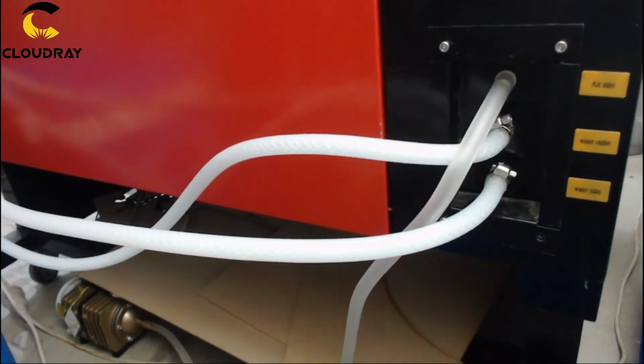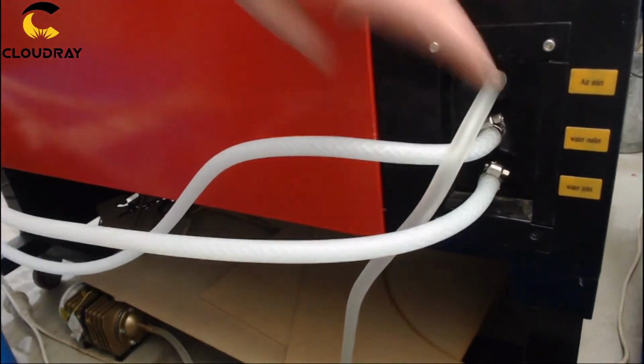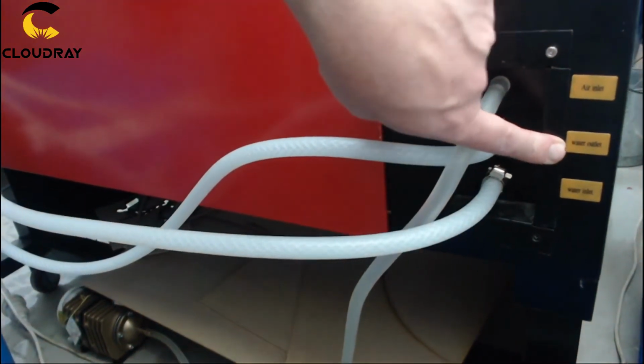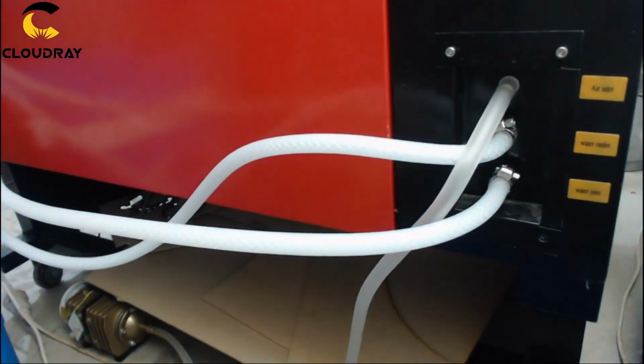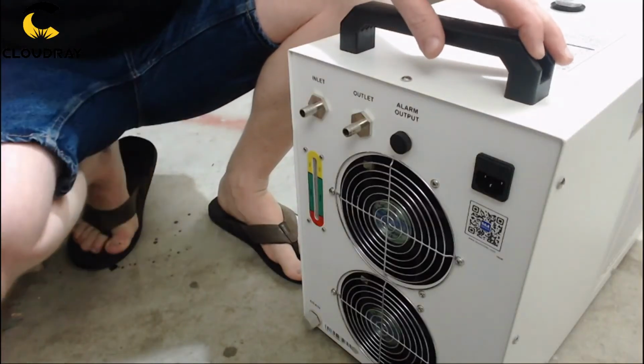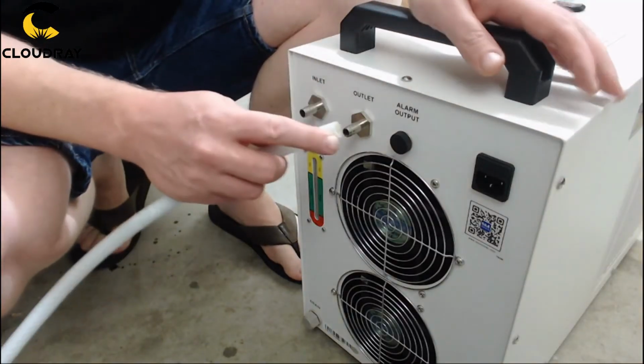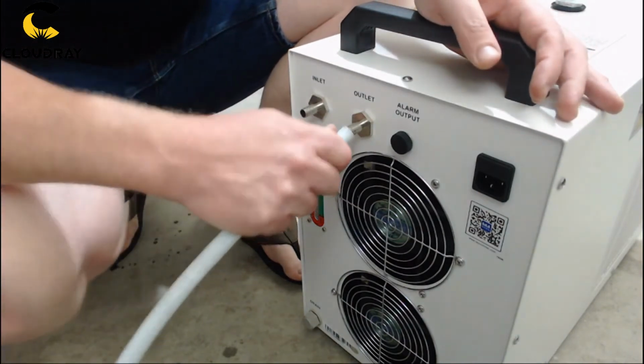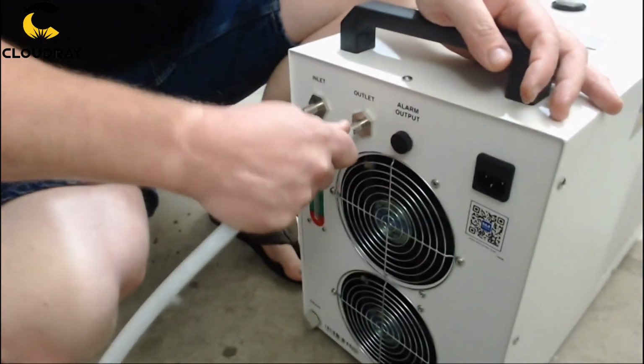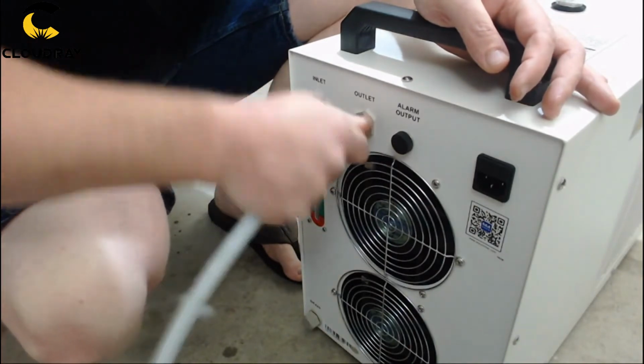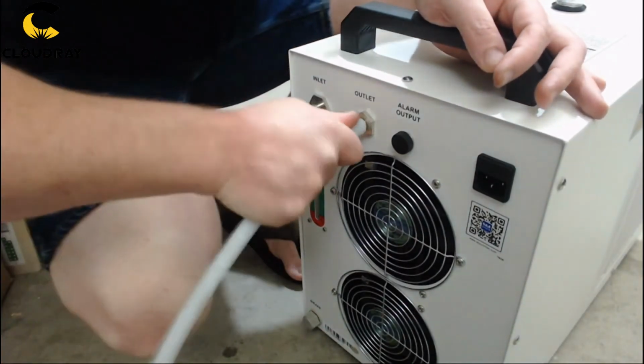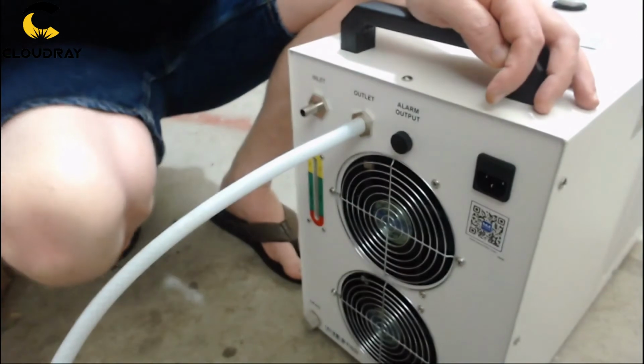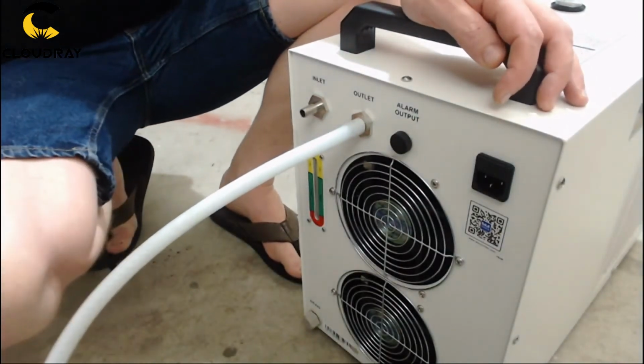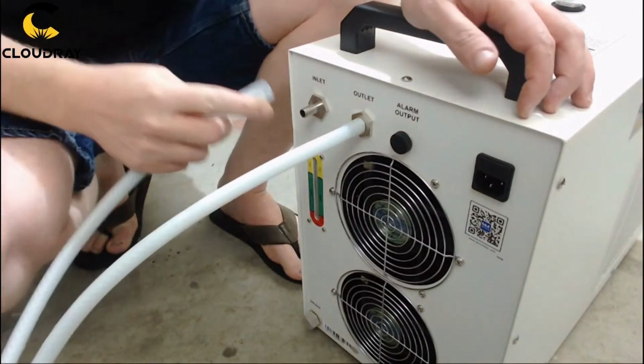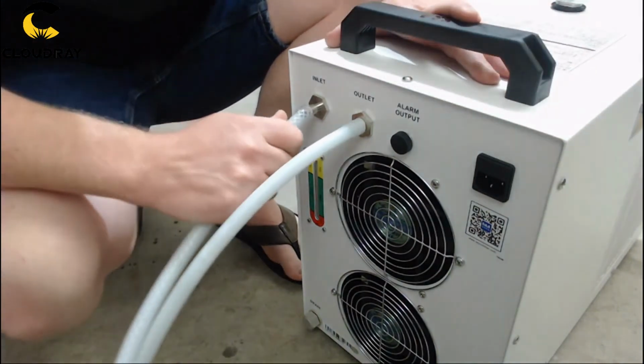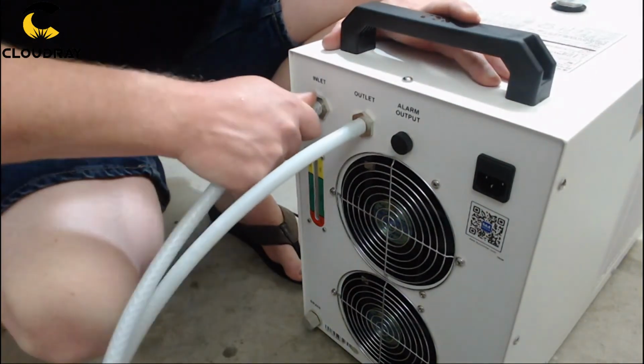Pay attention to the water inlet and water outlet hoses on your machine so that you can attach them at the right port on the chiller. So this is the water inlet hose, so it will attach to the outlet of the cooler. And the water outlet from the machine is going to be in to the chiller.